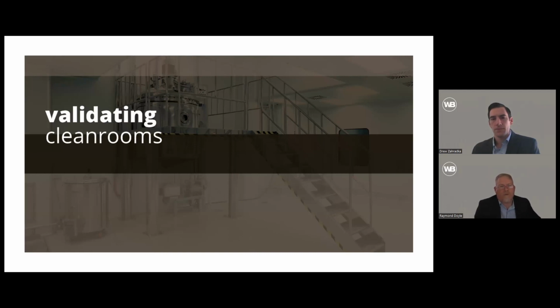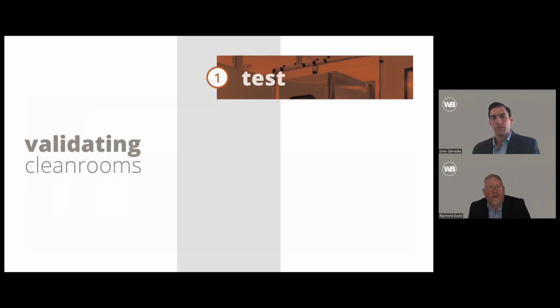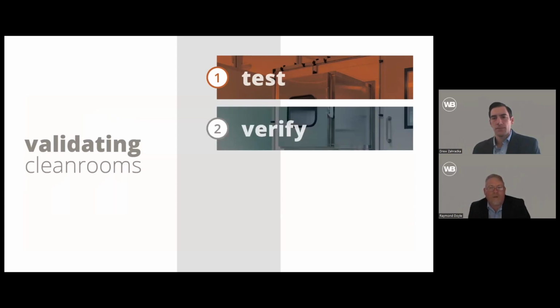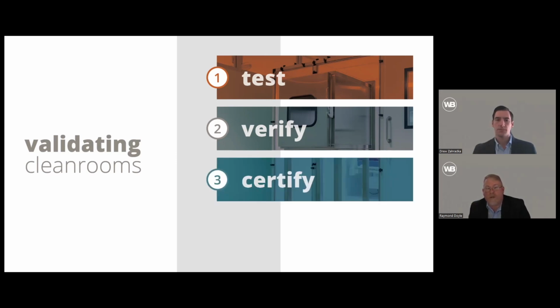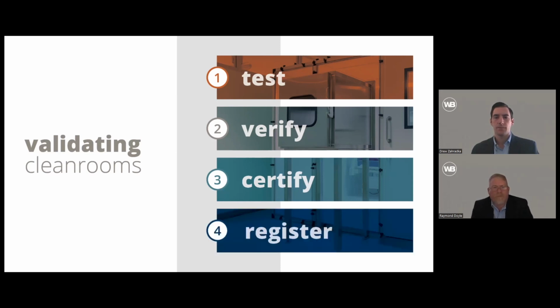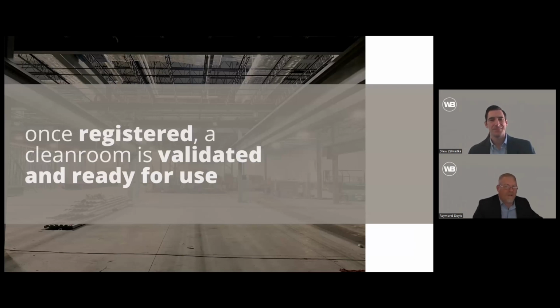We talked a little bit about validating clean rooms, but it's important to understand when you need to do it. Validating a clean room starts with the design early, and then we talk about the initial testing. And then from that testing, you verify the particle counts over a specific period of time. You might, again, have bacterial counts that you need to do in the case of certain classes of EU and FDA standards. And after that verification, you can then compile all of your data and issue that. This is all part of a validation process that you would typically use an external third party for, but some people have internal quality departments to manage this. And then you do all that certification and paperwork and submit it. And then you get registered and you can actually start using your clean room. Once registered, you get the validation and you get your certifications, wherever that may be in whatever industry that may be in, and you're ready for use.